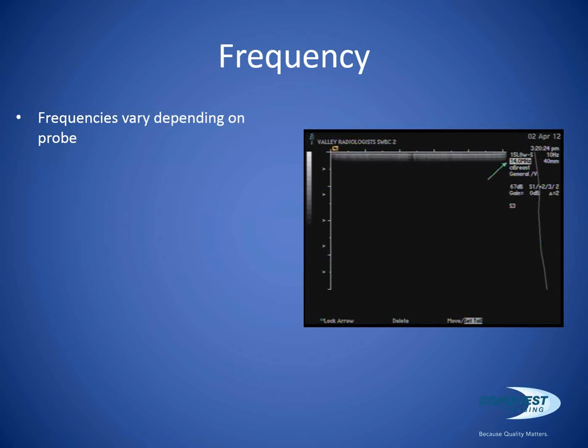So frequencies do vary depending on the probe. The probe type typically, with higher frequencies, we're looking at small parts like breasts and testicles and thyroids, musculoskeletal work. Lower frequencies are typically for abdomens. The thing about frequency is we get into talking about ultrasound physics. Lower frequencies give you better penetration, but lower resolution because of the wavelength of the pulse going into the body. So the upside of low frequencies is we can penetrate. So for a person with a very large body, we would want to go with a low frequency to penetrate that person. But the problem is we're going to lose resolution.